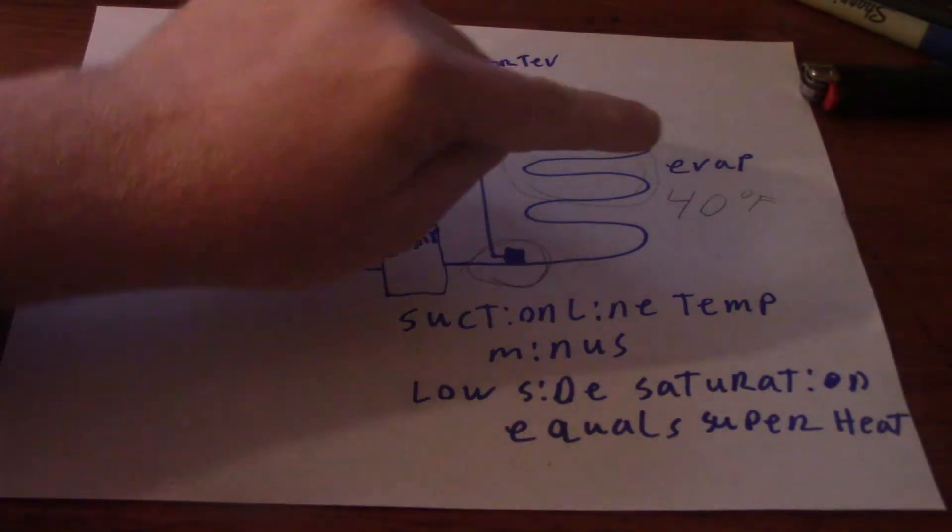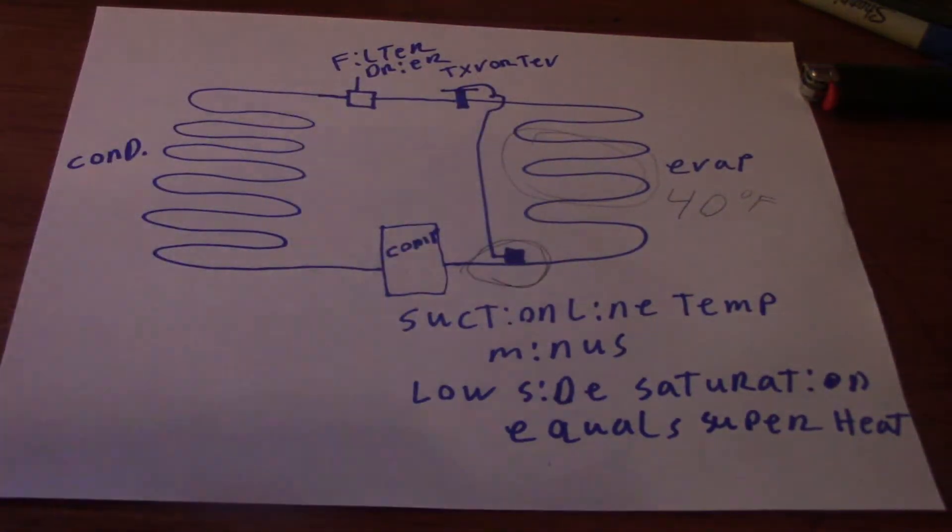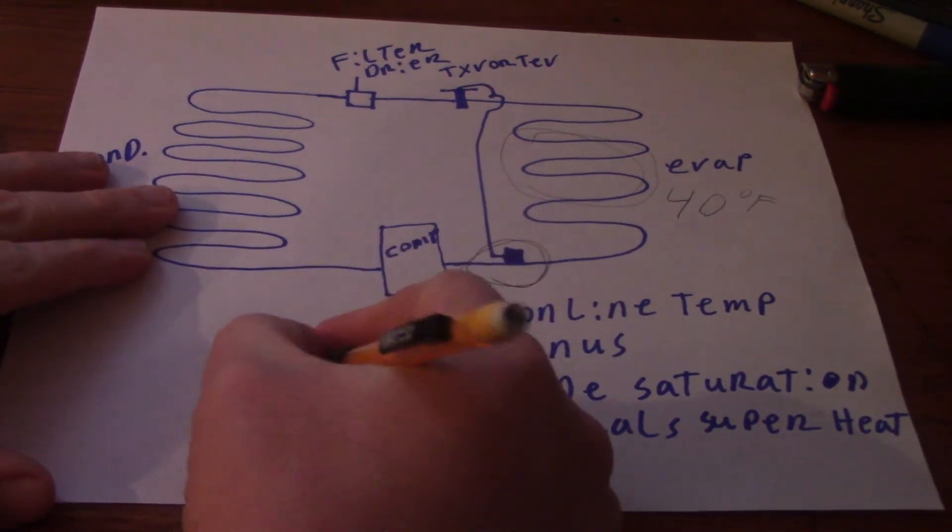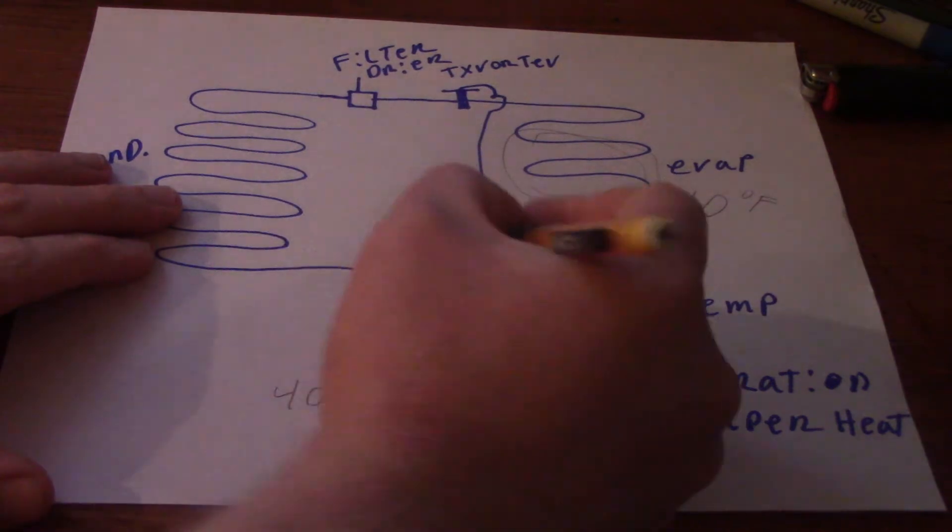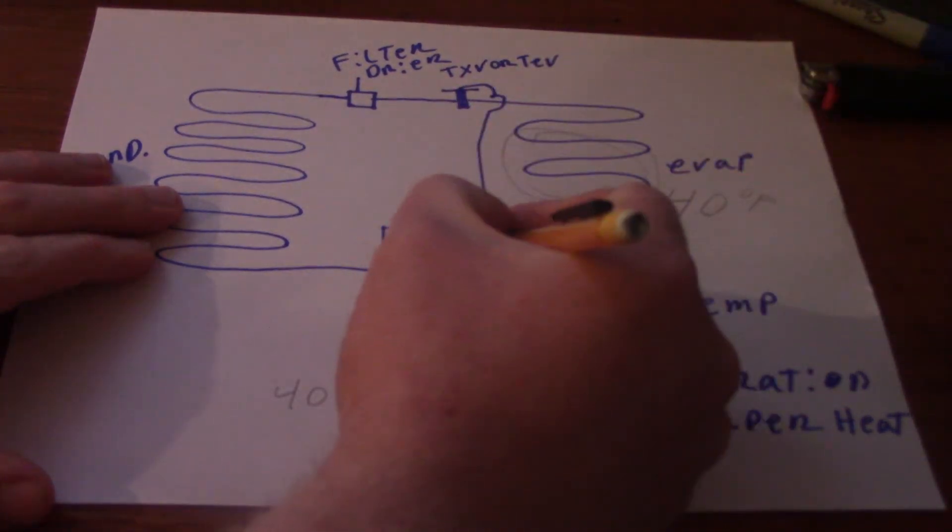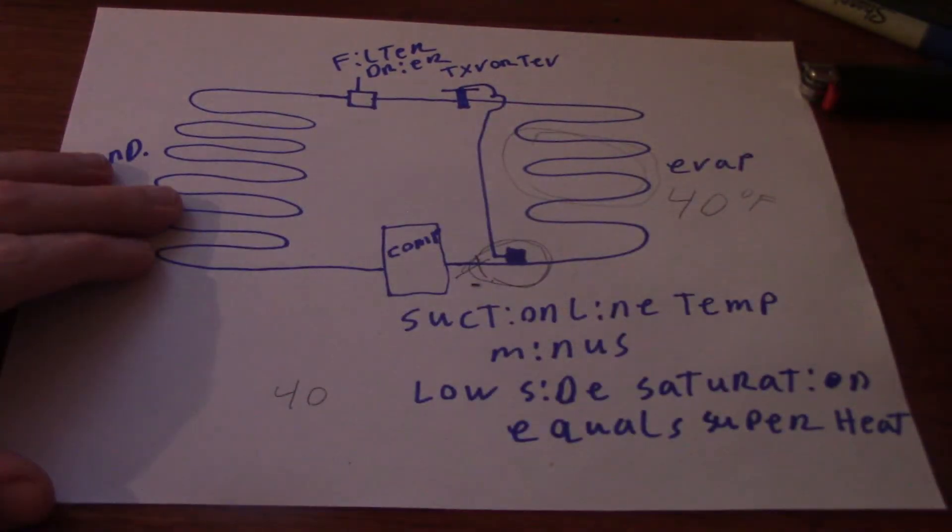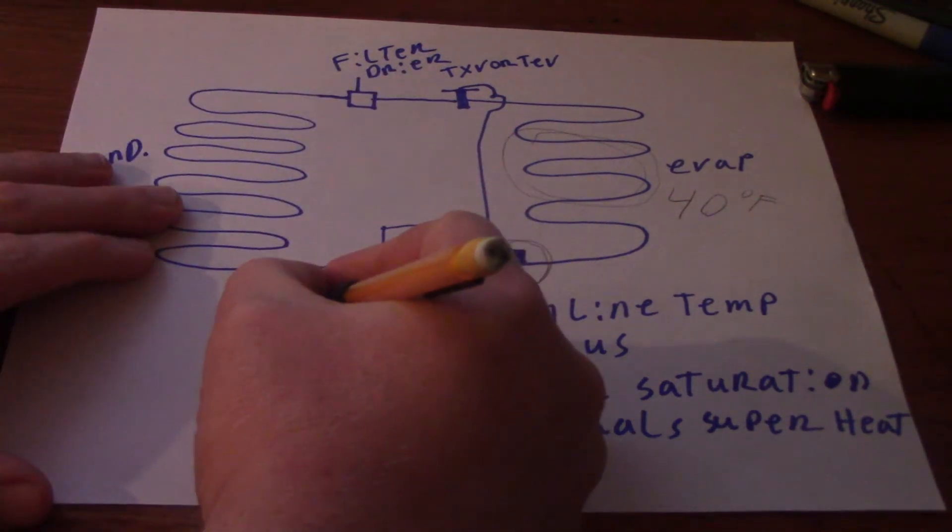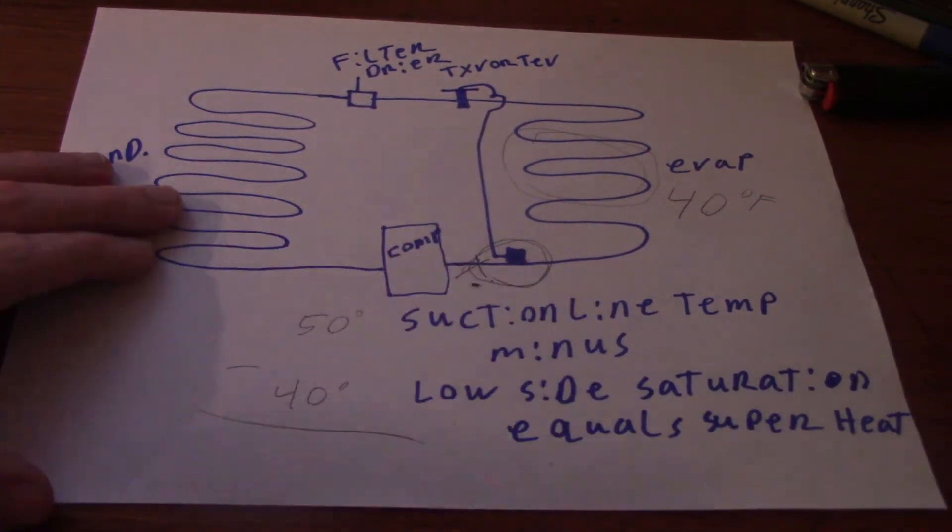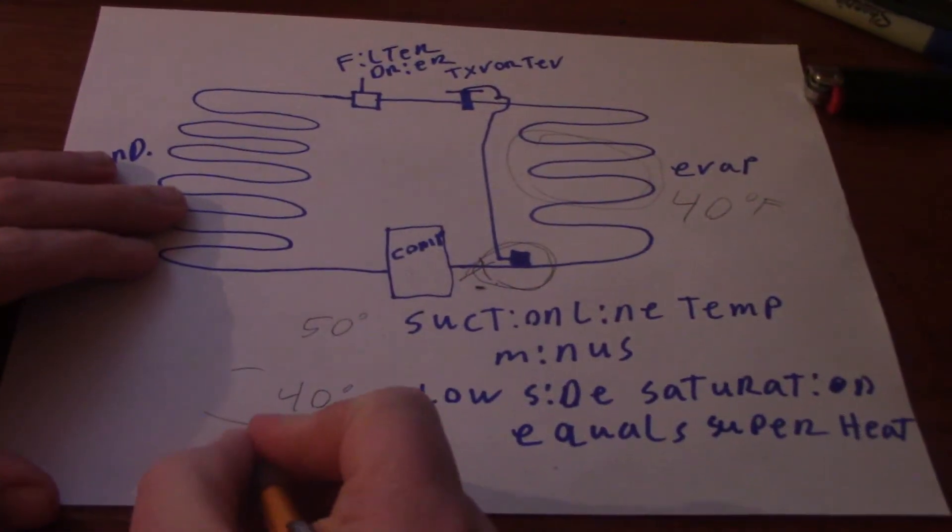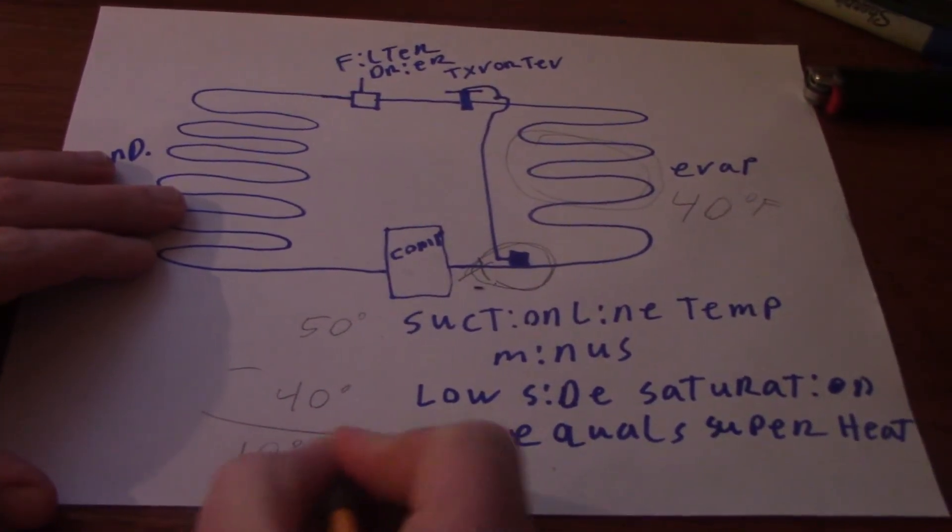So let's say we boiled off at 40 degrees there. So our saturation we'll put as 40 there. Let's say we put our temperature probe, broken pencil, hey there we go, look we're doing it, yay! We go right there for suction line temperature, and it was, we'll say 50 degrees Fahrenheit, minus, put our equal sign there, 50 minus 40, means the system's going to run with 10 degrees of superheat.